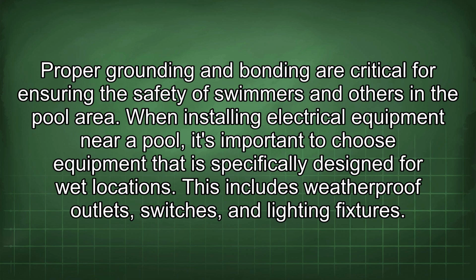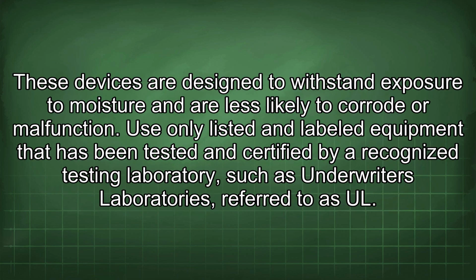When installing electrical equipment near a pool, it's important to choose equipment that is specifically designed for wet locations. This includes weatherproof outlets, switches, and lighting fixtures. These devices are designed to withstand exposure to moisture and are less likely to corrode or malfunction. Use only listed and labeled equipment that has been tested and certified by a recognized testing laboratory, such as Underwriters Laboratories, referred to as UL.